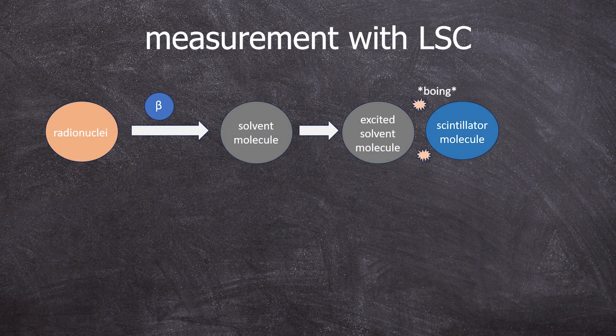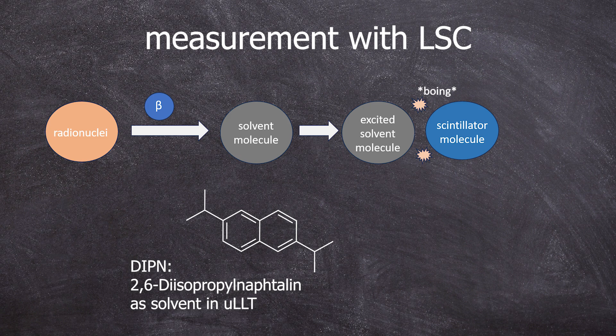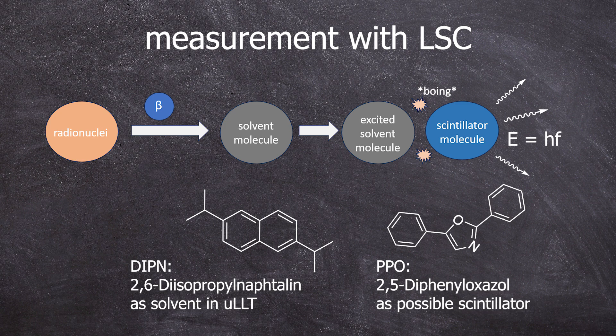Before I show you the spectrum, let me briefly explain how an LSC spectrum is generated. We have a radioactive sample that decays. The energy of the emitted beta particle excites the molecule of the aromatic solvent, causing them to collide with the scintillation molecules. These molecules then have excess energy and emit this energy in the form of light, which can be measured by detectors.